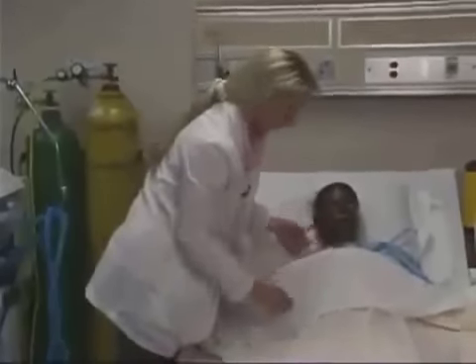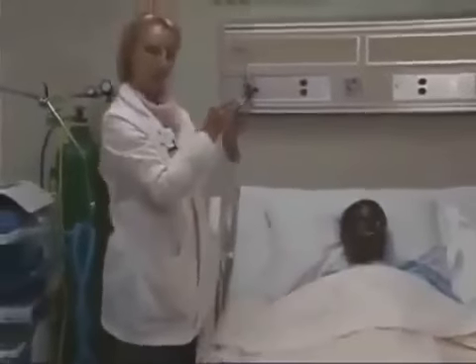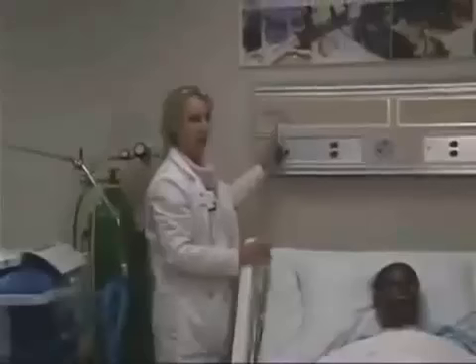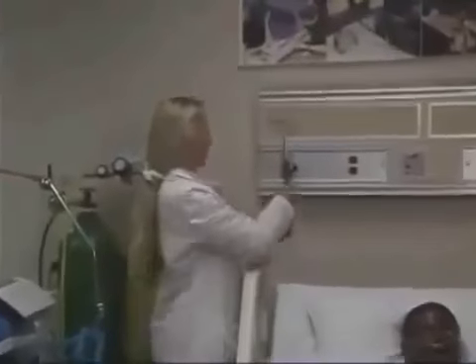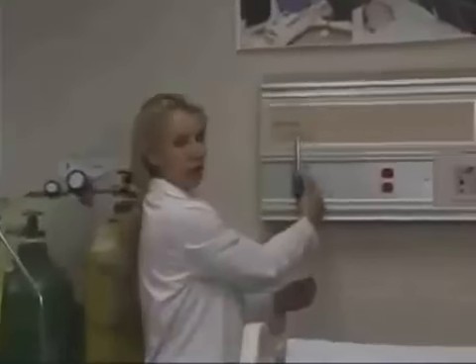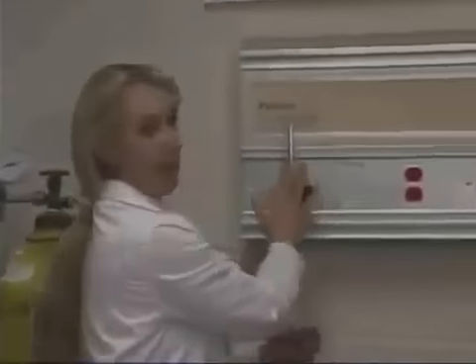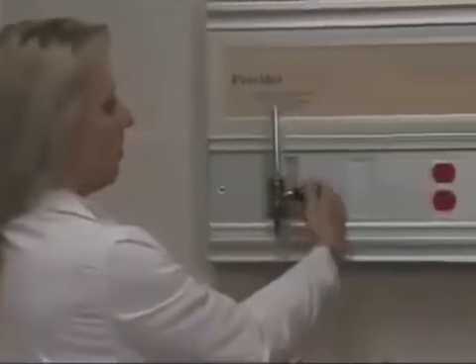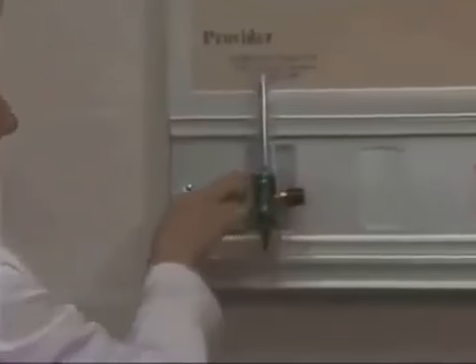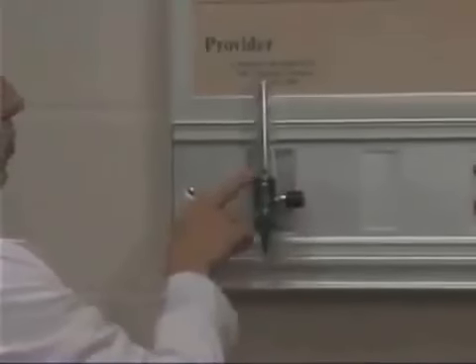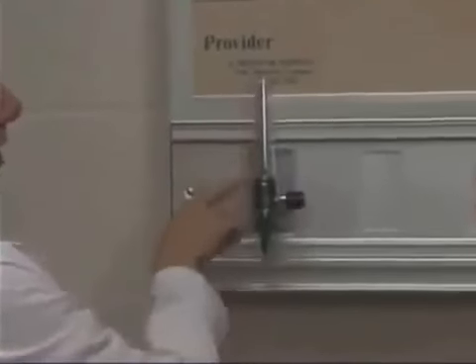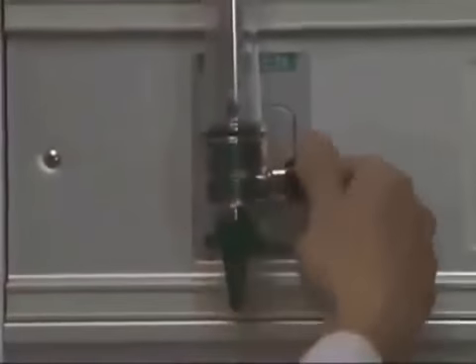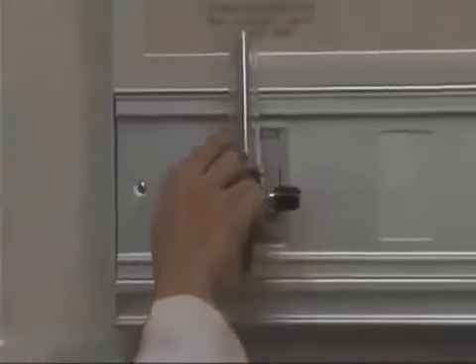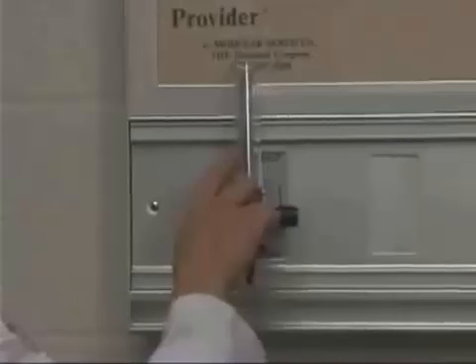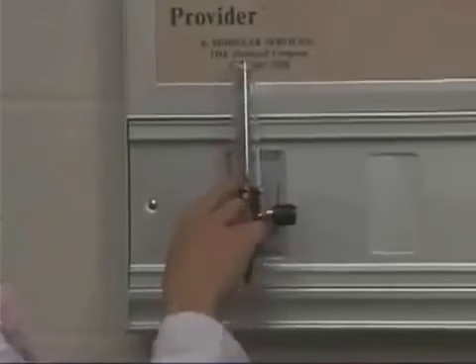So once it's on the patient, this end gets attached to the source of oxygen, which will be on the wall. This knob will turn the oxygen on or off. This isn't actually hooked up to the oxygen right now, but if you turn this to the right, there is a black ball in here, and this will rise. If you can see the numbers, it goes from 1 up to 15 on this flow meter. So as you turn this, you can adjust where this ball rises, and you need to set this according to the order you have as far as how much oxygen you're going to deliver to the patient.